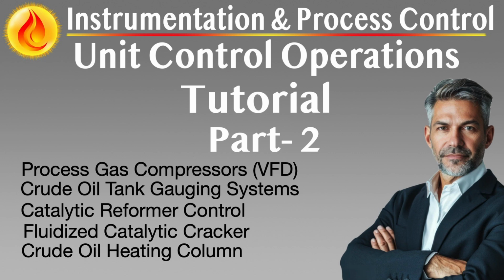These measurements are fed into advanced process control, APC, systems or model predictive control, MPC, layers that dynamically adjust hydrogen to hydrocarbon, H2/HC, ratios, feed rates, or heater duty to balance conversion and selectivity. When integrated with octane or product analyzers, the system can fine-tune severity in real time to meet reformate quality specs.